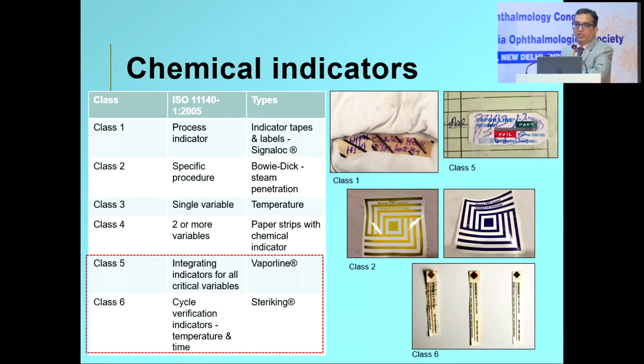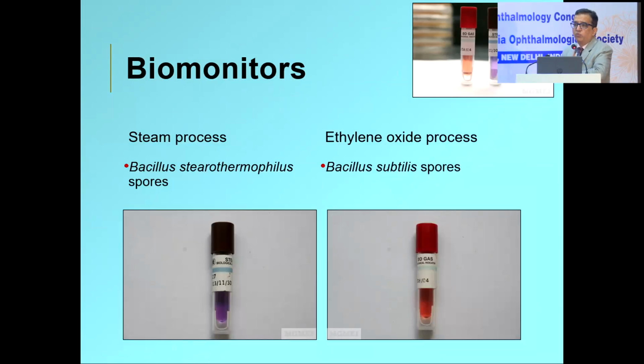Once a day in the morning, you run the Bowie-Dick, that it comes in a pack. You put it in your sterilizer without anything else, without any other load, and you let the sterilizer complete its cycle. Take it out, remove the sheets of paper, and then see whether the color has changed. If the color has changed, that means that machine, that autoclave is good enough for the entire day. Then you have biomonitors. So you need to also do a biomonitor test, and this doesn't need to be done daily. You do it once a week.